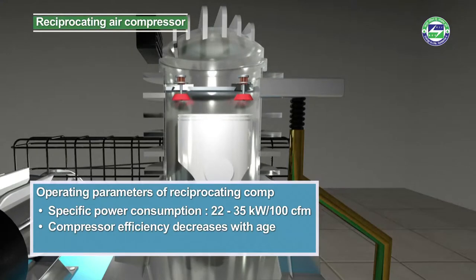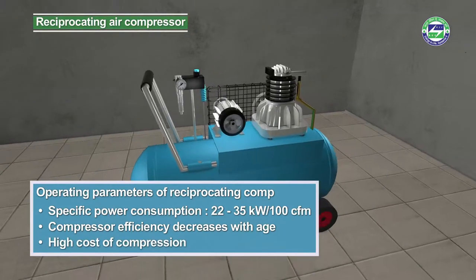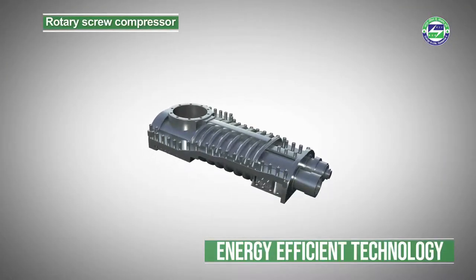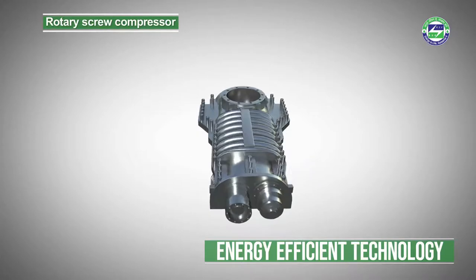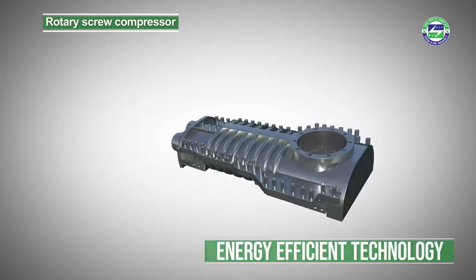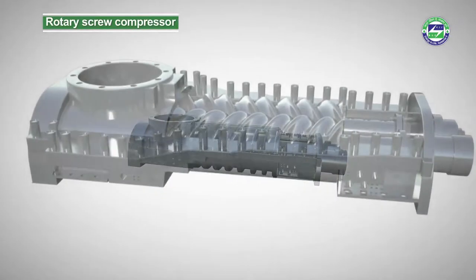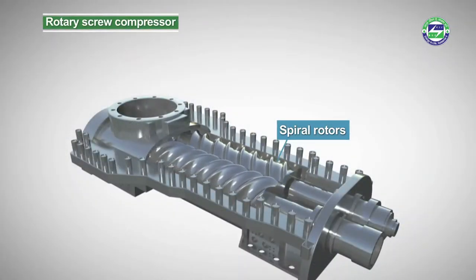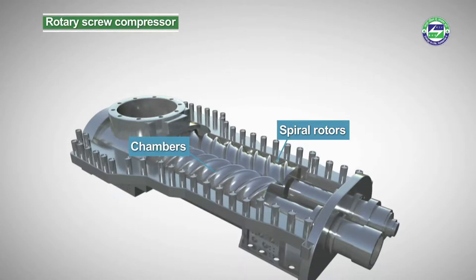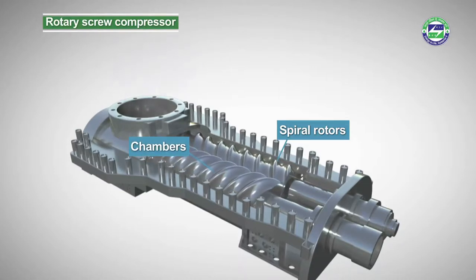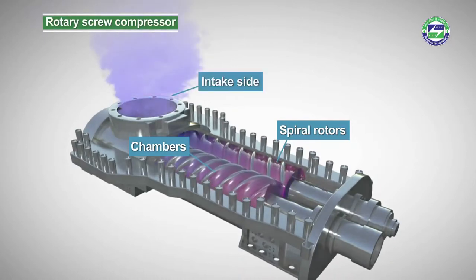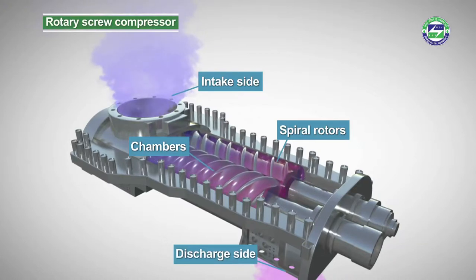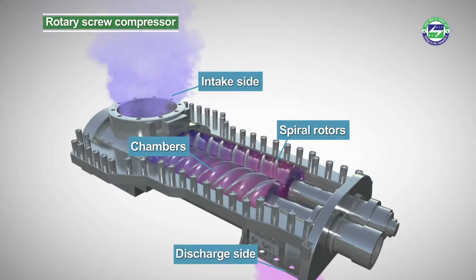These compressors produce a lot of noise with a relatively high cost of compression. Operational efficiency varies, ranging from 22 to 35 kilowatt per hundred CFM, and this goes down as the age of the equipment increases. Energy-efficient rotary screw compressors function on the basic principle of a positive displacement machine, in which the key elements are a pair of spiral rotors. During operation, the rotors turn and the spiral keys mesh together, forming chambers between the rotors and the casing wall.